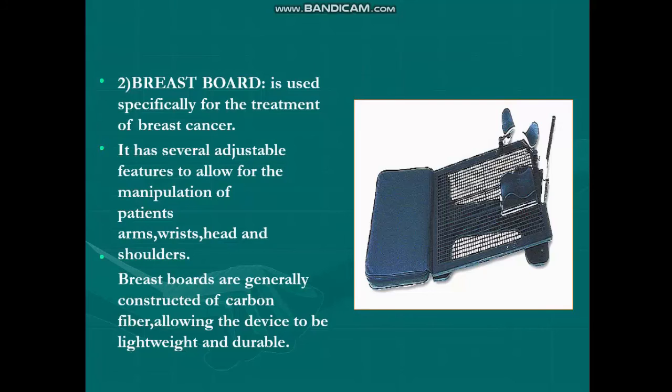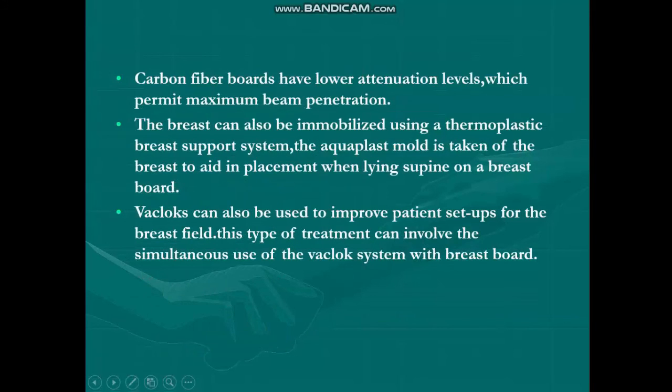It has several adjustable features to allow for the manipulation of patients' arms, wrist, head and shoulders. Breast boards are generally constructed of carbon fiber, allowing the device to be lightweight and durable. In this picture you can see a breast board for immobilization of a patient with breast cancer during radiotherapy. Carbon fiber boards have low attenuation levels which permit maximum beam penetration.